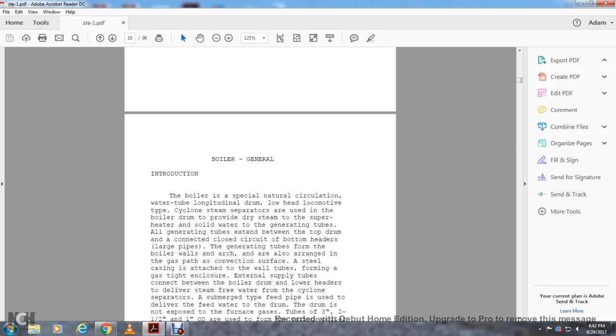The generator tubes extend between the top of the drum, connected in a closed circuit with the bottom header by large pipes. Generator tubes from the boiler walls and arch are also arranged in the gas path as a convection surface. The steel casing is attached to the wall of the tubes, forming a gas-tight enclosure with external supply system tubes. These connect the boiler drum with the lower headers to deliver the steam-free water from the cyclone. A separate submerged type of feed is used to deliver the feed water to the drum.